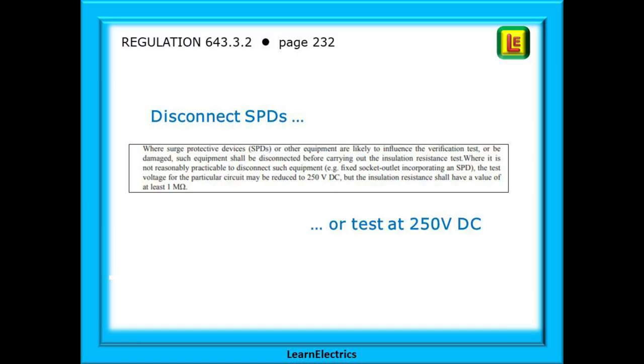Regulation 643.3.2 on page 232 of the wiring regulations book tells us that SPDs and AFDDs etc. should be disconnected from the circuit before testing. In the case of an SPD when testing at 500 volts, the device will try to limit the voltage to 250 volts — since that is its job — and the circuit will fail. Devices such as AFDDs may also be damaged by the test and they are not cheap to replace.